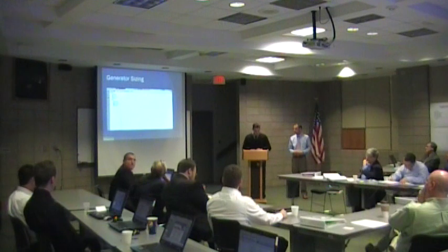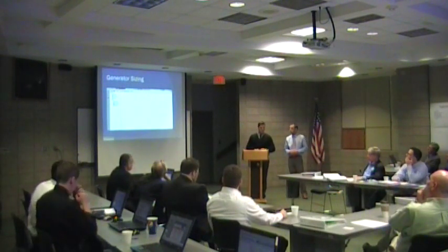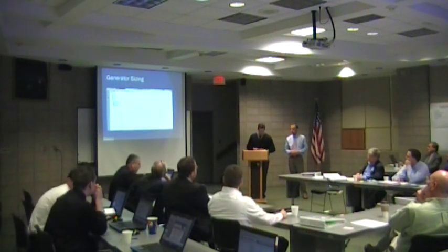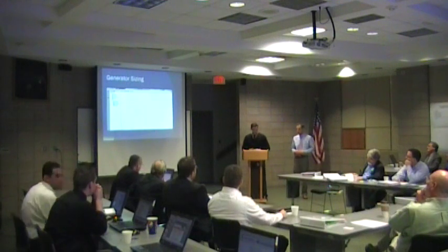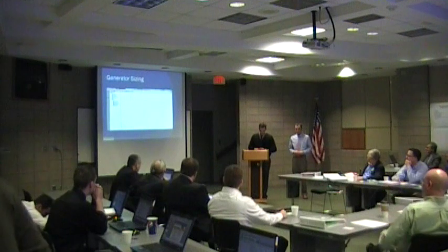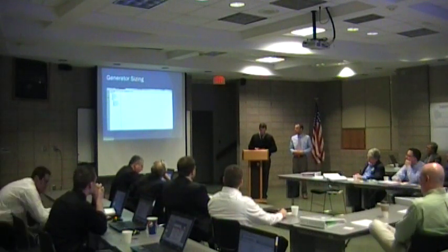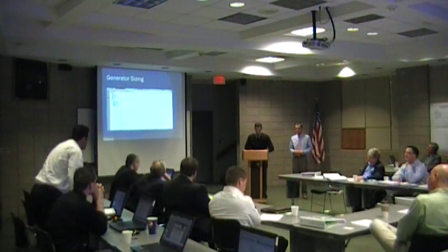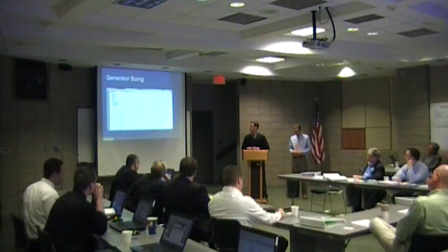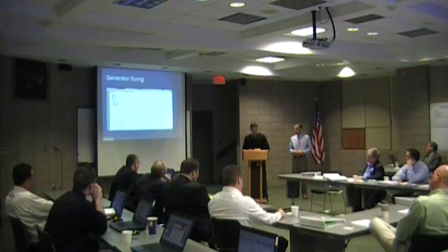This is a snapshot of the Cummins Power Suite software that we use to size our generator. The snapshot shows all the loads on the left that will be on this generator, which include the lighting panel, the receptacle panel, the air handling unit, two condensing units, one for now and one for future expansion, and also two boiler pumps. It also shows right below that all of these loads will be on the same step, starting at relatively the same time.